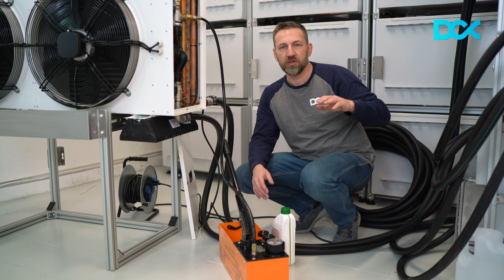Probably you will be standing with that on the same level, but for now, for the sake of convenience, we elevated the dry cooler, which means that the dry cooler is the highest placed, for the air release. And you may notice that if there will be an enclosure inside and the dry cooler, usually the enclosure is a little bit lower than the dry cooler. So this would be the place where you will be releasing all the air from the system. If the enclosure will be higher, make sure that before the startup you lift the dry cooler a little bit and make sure that the dry cooler is higher, so all the air will be released. The procedure is very simple, in terms of pressurizing it.